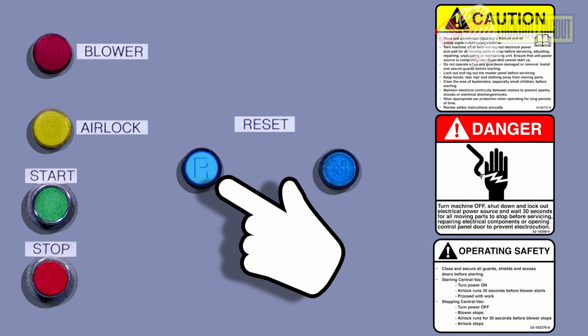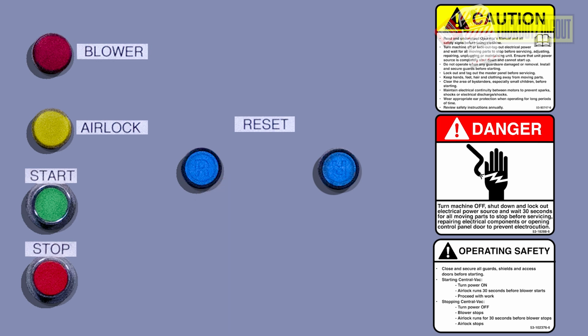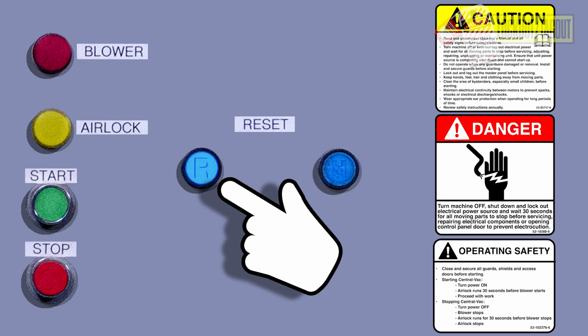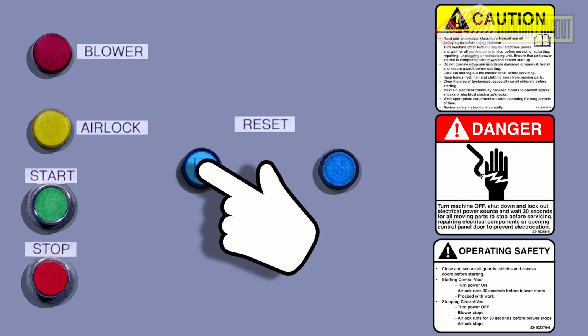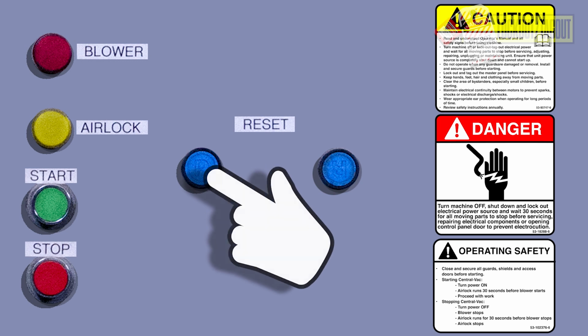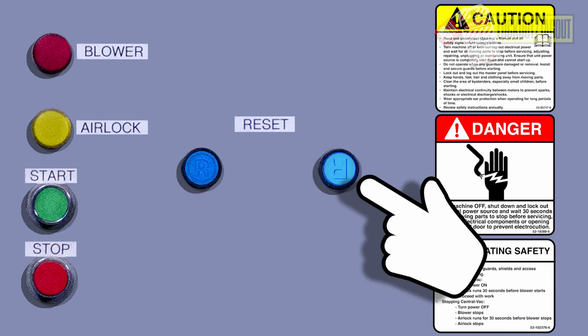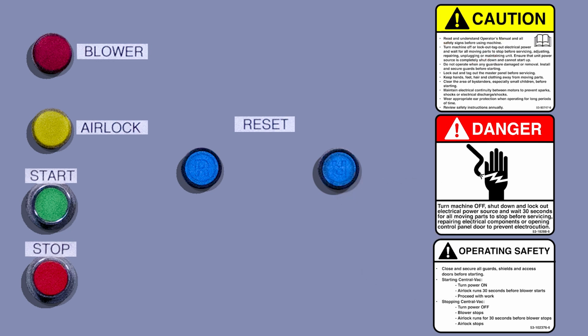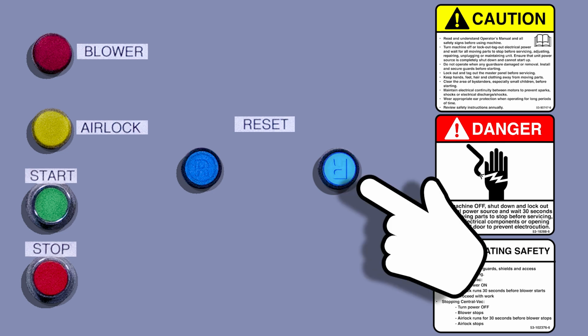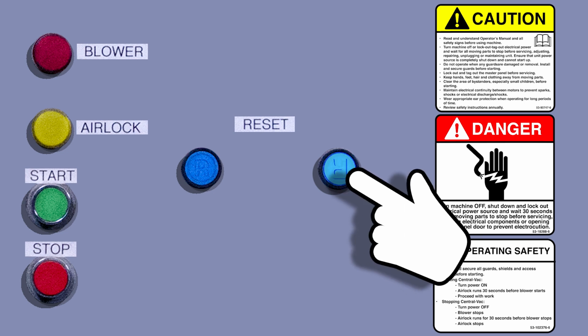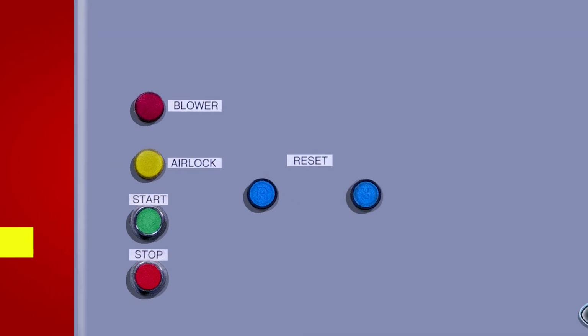Reset blower left. This lighted switch monitors the status of the blower's circuit breaker inside the panel. For normal operation, the light is off. If the blower circuit becomes overloaded, the circuit breaker will trip and this switch will be illuminated. Correct the problem, and then depress the switch to reset the breaker. Reset airlock right. This lighted switch monitors the status of the airlock circuit breaker inside the panel. For normal operation, the light is off. If the airlock circuit becomes overloaded, the circuit breaker will trip and the switch will be illuminated. Correct the problem and depress the switch to reset the breaker.